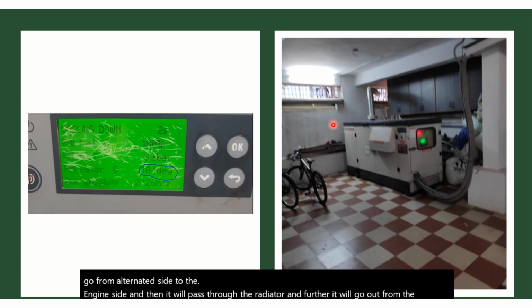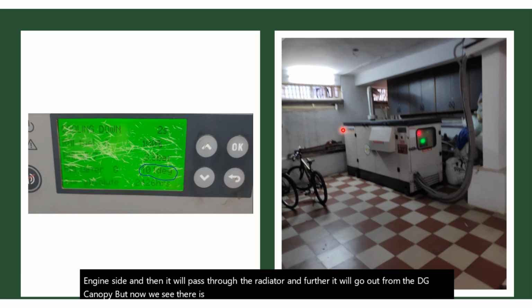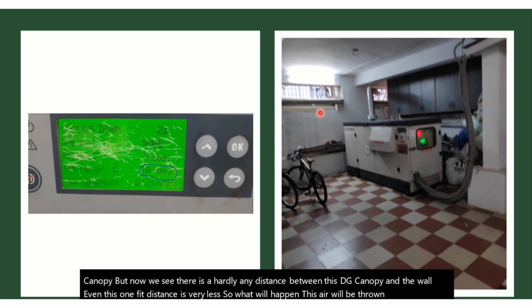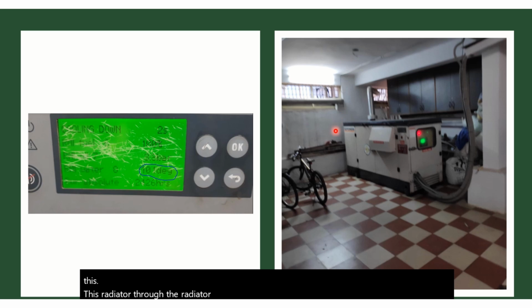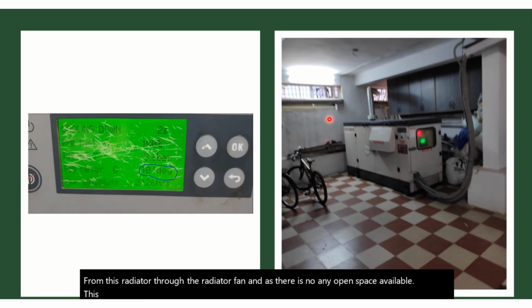But now we see there is hardly any distance between this DG canopy and the wall. Even this 1 foot distance is very little. So what will happen is, this air will be thrown out from the radiator through the radiator fan, and as no open space is available, this air will strike the wall, come back, and again get sucked into the suction.